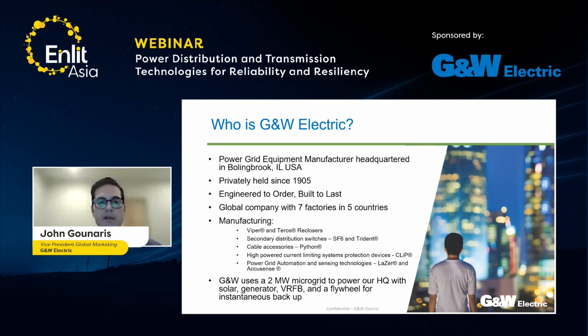We carry a very unique high-powered current limiting system protection device known as the CLiP. This is a medium voltage device with extremely high continuous current, thousands of amps, very high fault interrupting rating, and a unique capability that acts like a current limiting fuse, quickly removing very high fault currents from your system, thereby protecting your overall distribution.